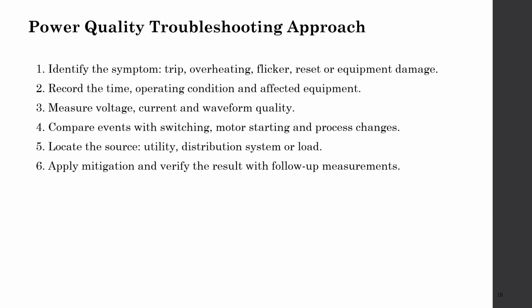Power quality troubleshooting approaches. We can talk about it step by step. First, identify the symptoms: trip, overheating, flicker, reset or equipment damage. Record the time, operating condition, and affected equipment. Measure voltage, current, and waveform quality. Compare the event with switching, motor starting, and process changes. Locate the source: utility, distribution system, or load. Apply mitigation and verify the result with follow-up measurement.